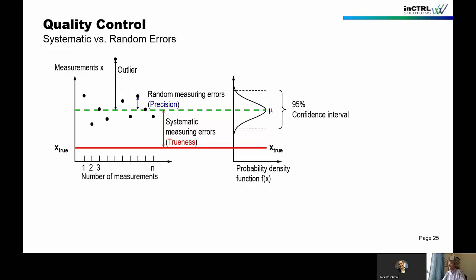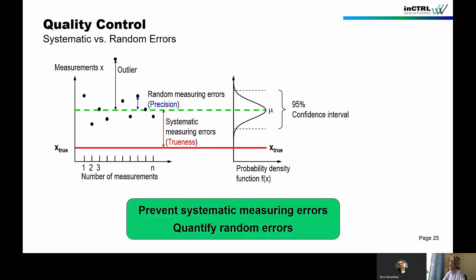However, in fact, the red line is the true value, right? And then the difference between the red and the green line, that is a systematic error, and we call that trueness. Very important. We want to prevent systematic measuring errors, and we want to quantify random errors. Random errors, you can work on that by changing, for example, installation, as we saw, but very often that is linked to the measuring principle. So you will never get completely rid of the random error. So you have to be aware of that.